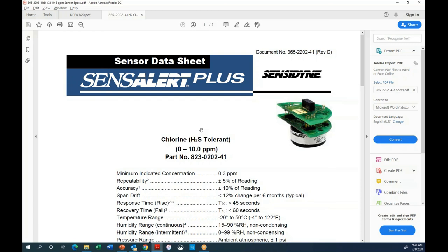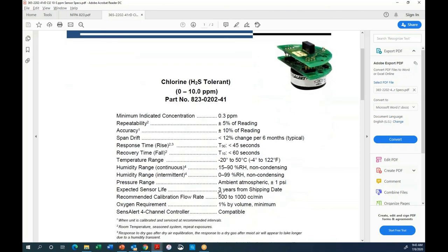And then to further on that, you can use the sensor life remaining in the menu structure to get an idea of how much longer that sensor will last you. And if you're doing your own calibrations, that's a really good thing to add to your calibration procedure, is to record that value. That way, say you're doing quarterly calibrations, you can get an idea of how much that sensor life is decreasing per quarter. And then once you get below a certain value, it might be a good time to get a new sensor on order, so you don't run into a situation where you don't have a working sensor.